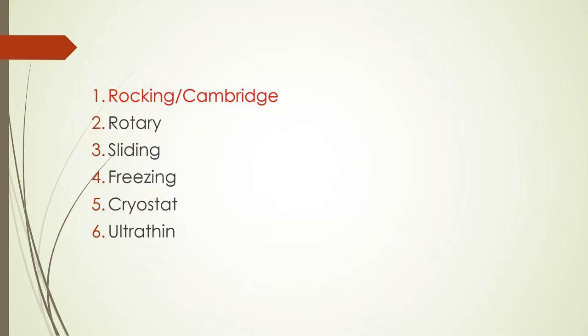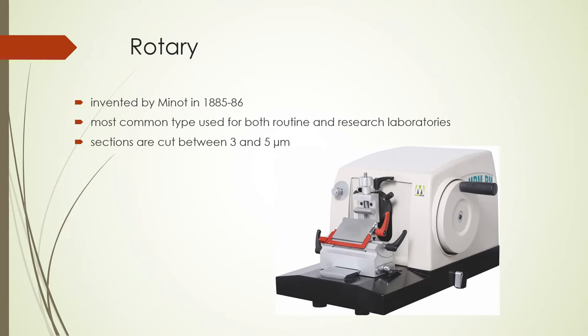Next, we have the rotary microtome — the most common type of microtome used for both routine and research laboratories. It was invented by Minot in 1885 to 1886 and can cut sections between 3 to 5 microns, which is pretty decent for routine purposes already.